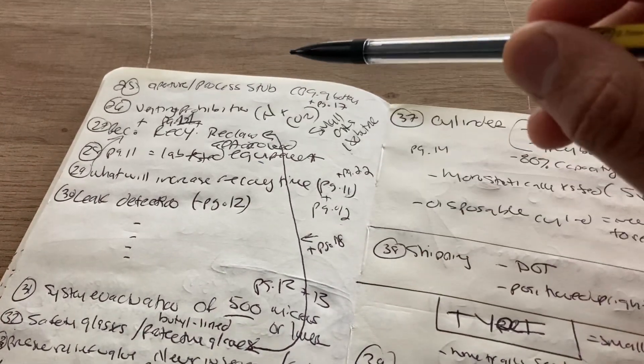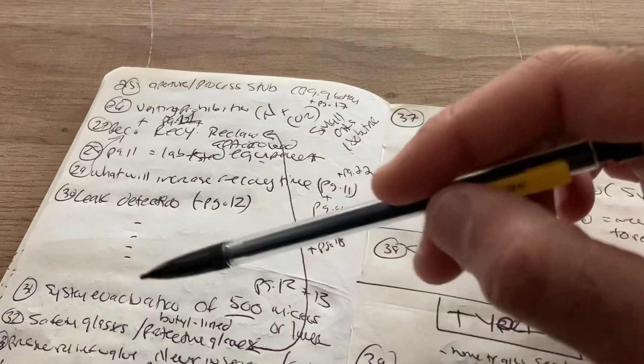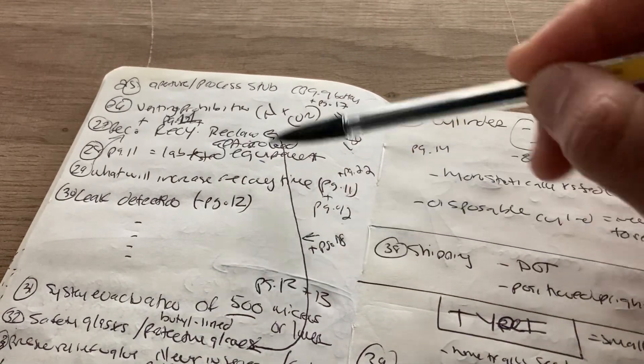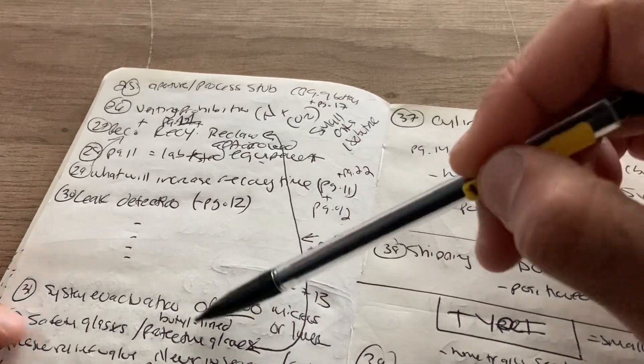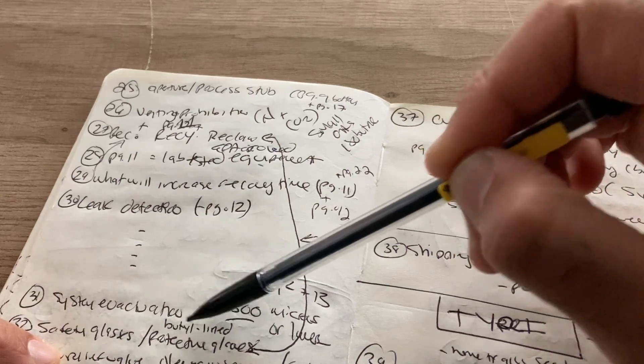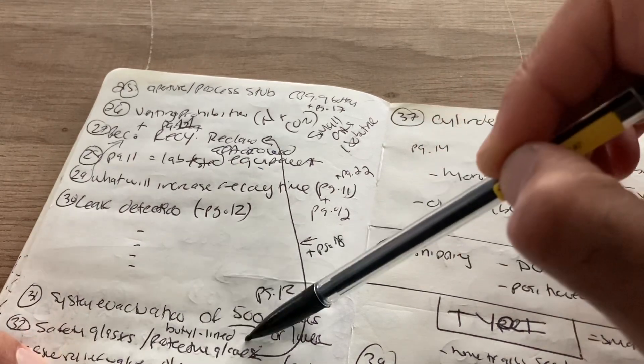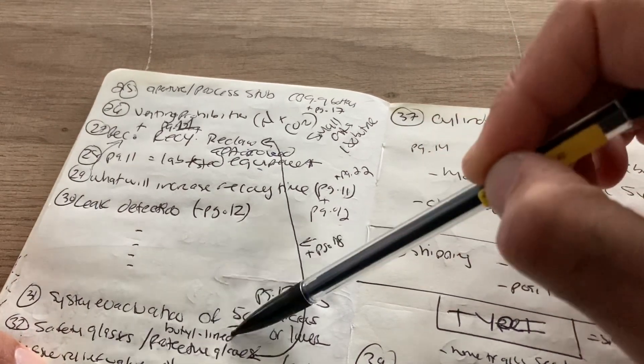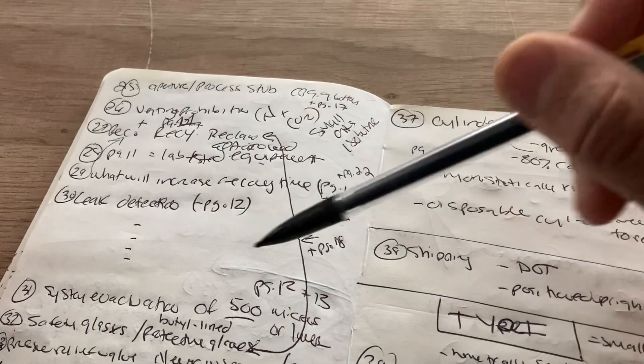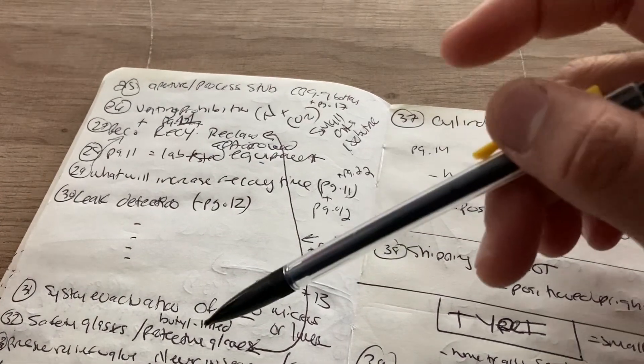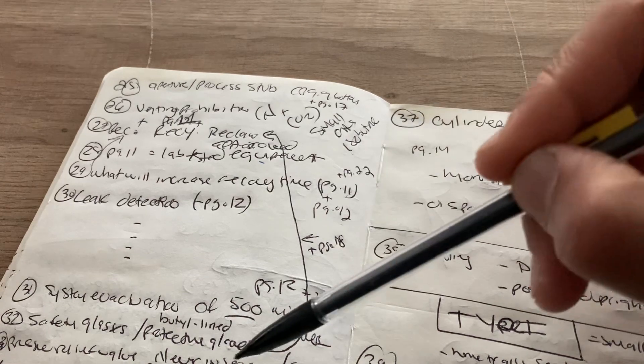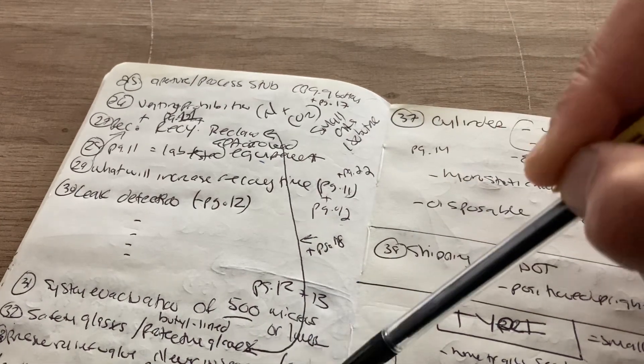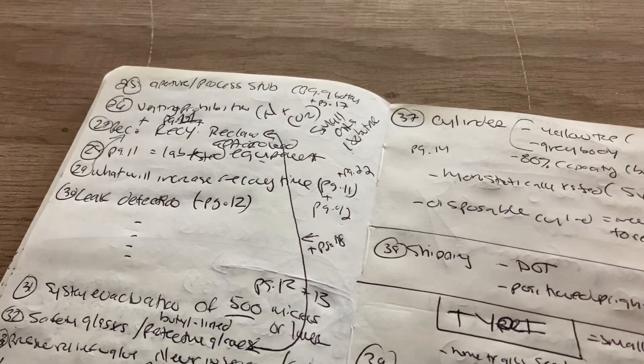So when it comes to safety equipment, they're going to say safety glasses and protective gloves when it comes to recovery, when it comes to reclaim, but they may also may add in butyl-lined, B-U-T-Y-L, butyl-lined. If that's not there, then the answer is probably just protective gloves. Pressure relief valve is never in series. It's always in parallel, only parallel, never in series, only in parallel. So pressure.